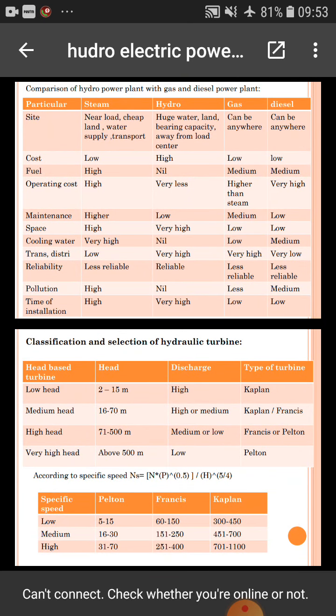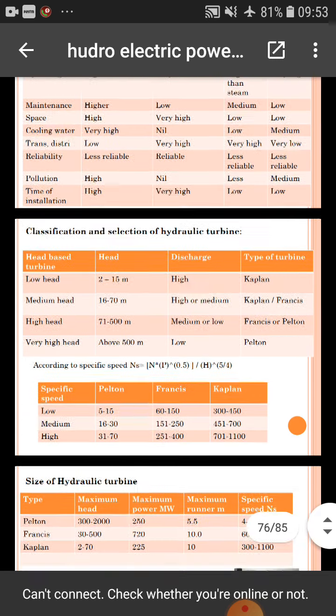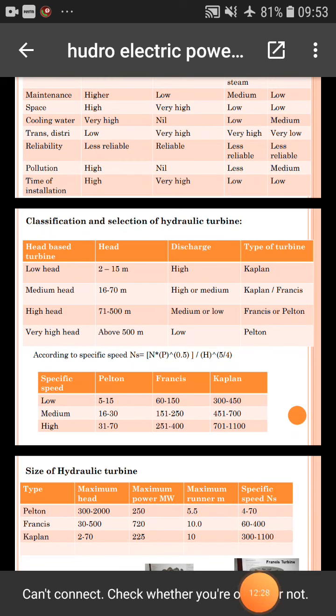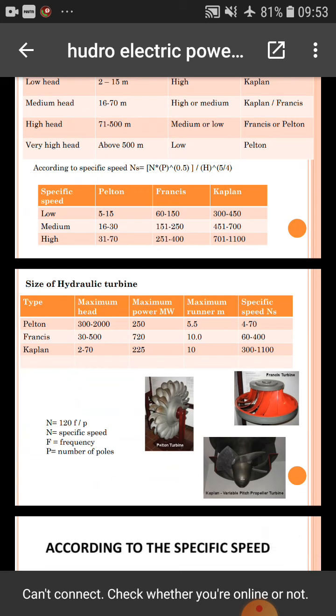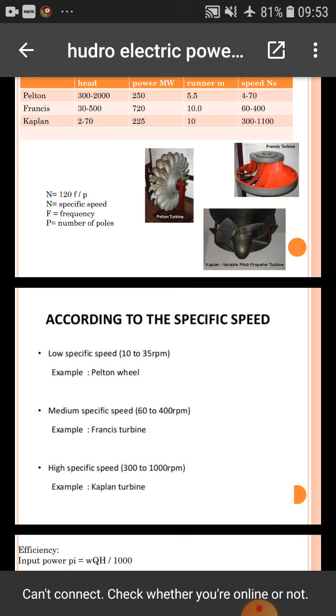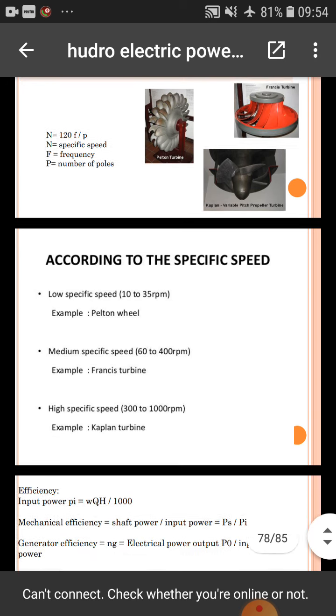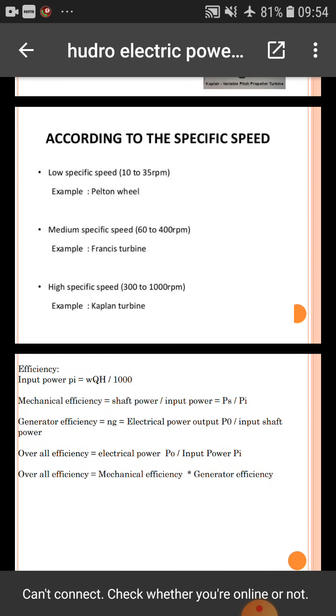Classification and selection of hydro turbines: turbines are classified by head, discharge, and type. The size of hydro turbines is shown in figures. Types include Pelton wheel, Kaplan turbine, and Francis turbine. By specific speed classification: low specific speed 10 to 35 rpm — Pelton wheel; medium specific speed 60 to 400 rpm — Francis turbine; high specific speed 300 to 1000 rpm — Kaplan turbine.